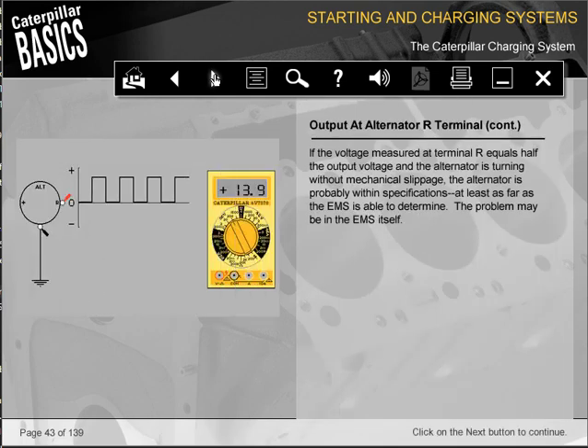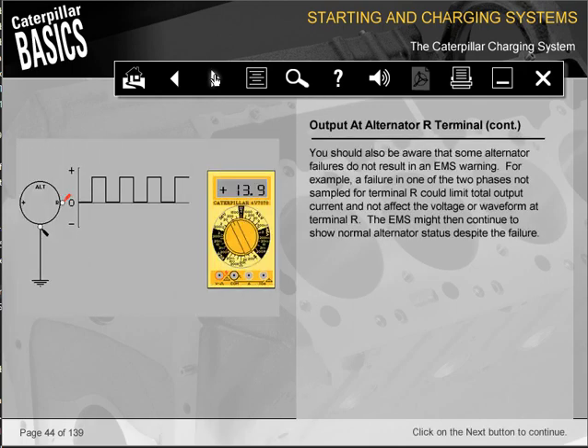If the voltage measured at terminal R equals half the output voltage and the alternator is turning without mechanical slippage, the alternator is probably within specifications, at least as far as the EMS is able to determine. The problem may be in the EMS itself. You should also be aware that some alternator failures do not result in an EMS warning. For example, a failure in one of the 2 phases not sampled for terminal R could limit total output current and not affect the voltage or waveform at terminal R. The EMS might then continue to show normal alternator status despite the failure.